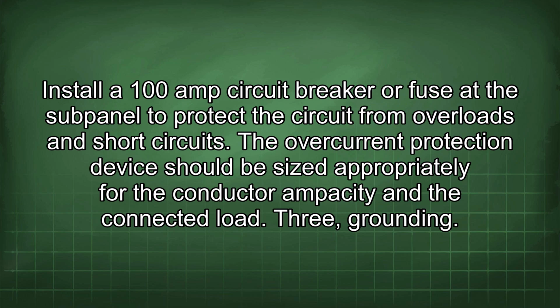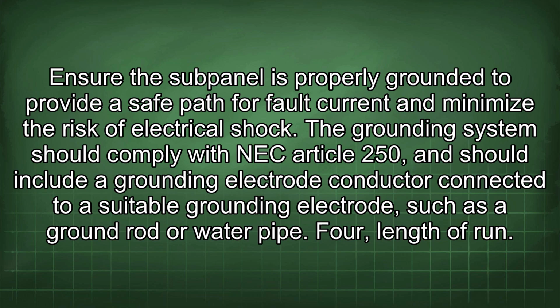3. Grounding. Ensure the subpanel is properly grounded to provide a safe path for fault current and minimize the risk of electrical shock. The grounding system should comply with NEC Article 250 and should include a grounding electrode conductor connected to a suitable grounding electrode, such as a ground rod or water pipe.